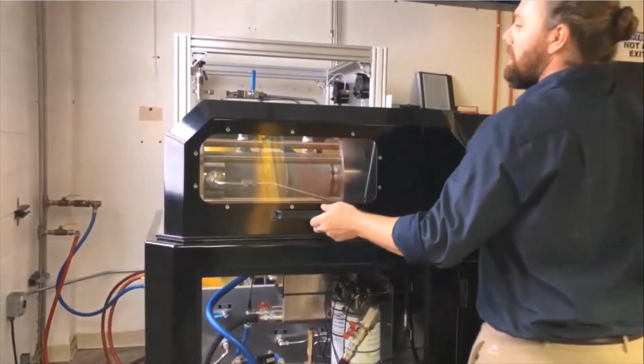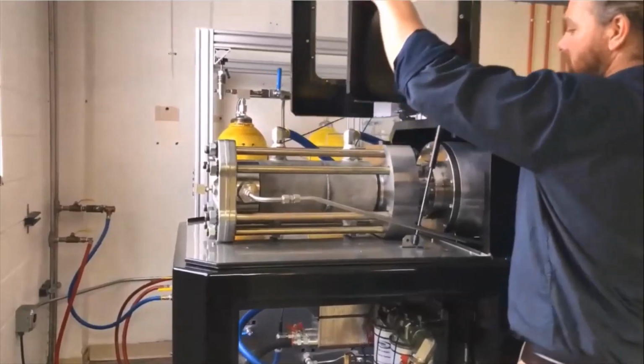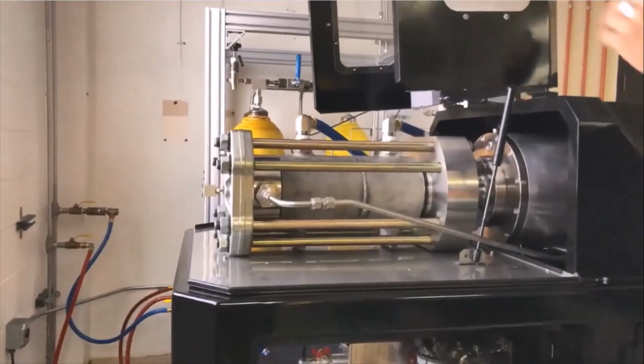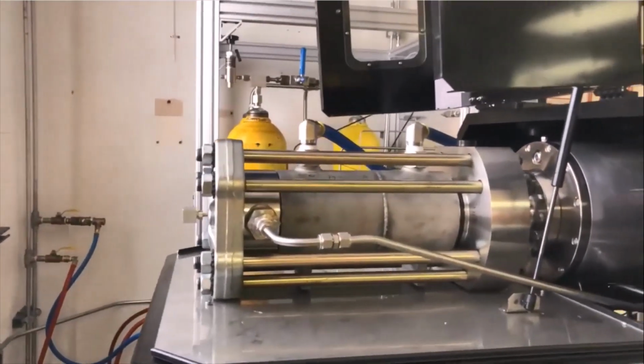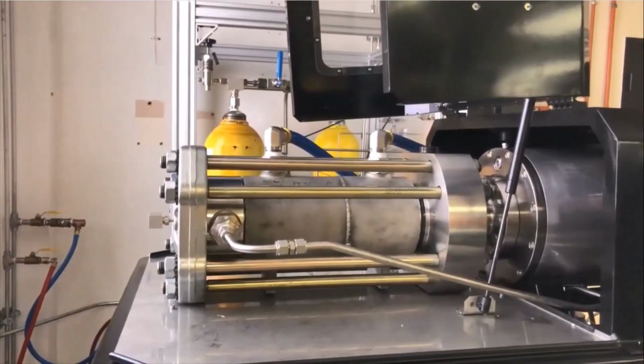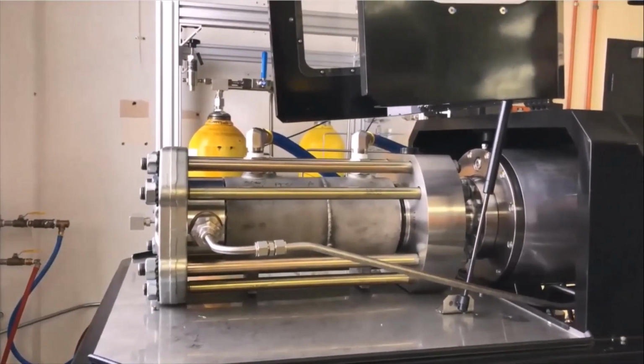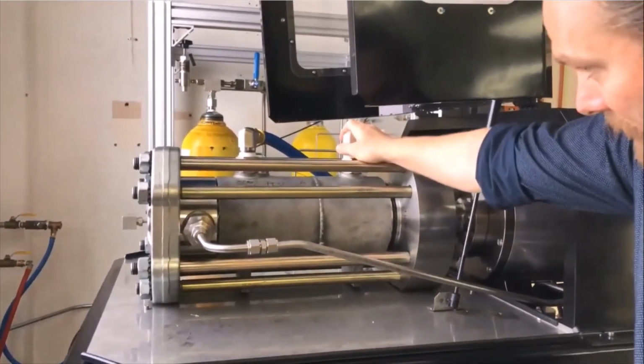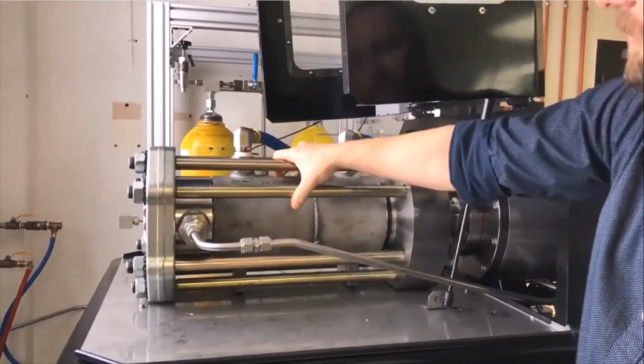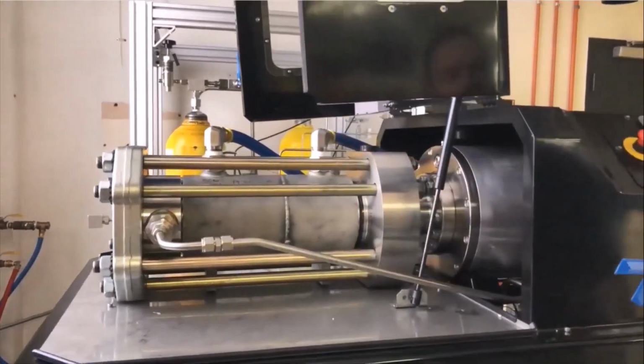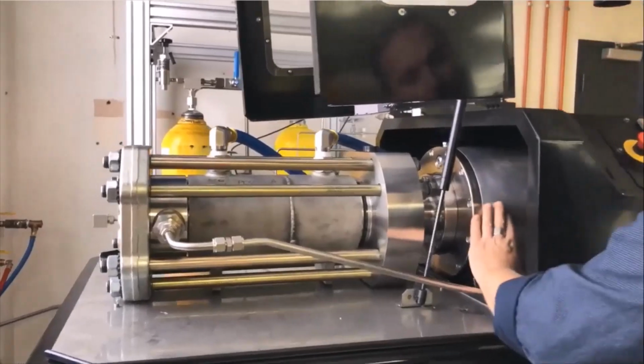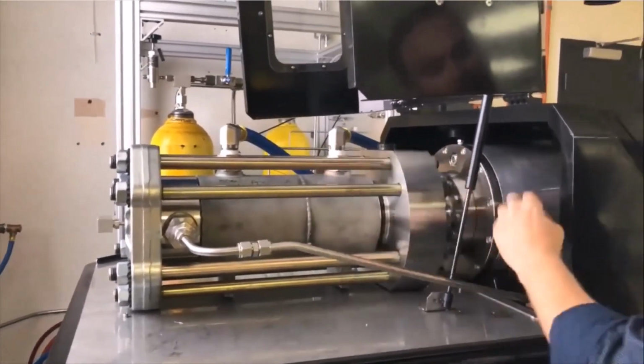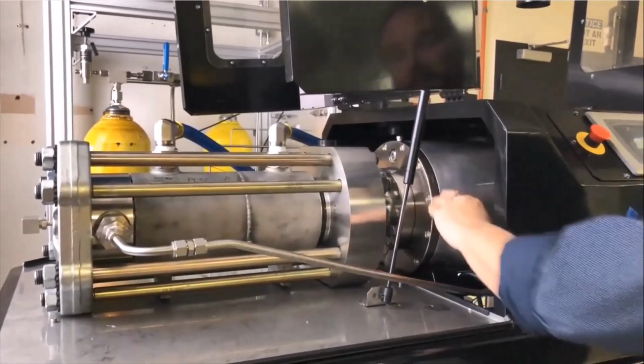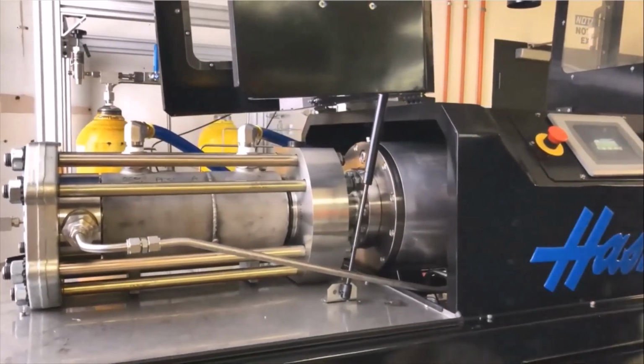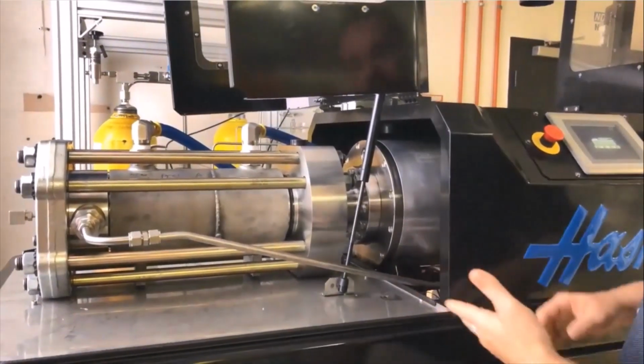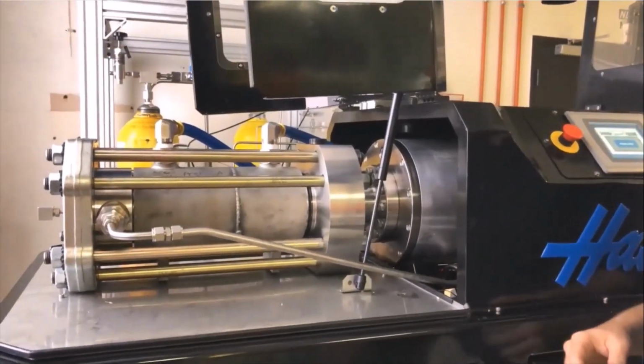Up top here, let's go through the gas sections. Right now we're looking at a single stage double acting gas booster. This is the QGD 90. Again, here's your cooling circuit going through the cooling jackets. Your servo drive. We have our distance piece gas section. The distance piece ensures there is no oil getting into your gas section. The oil is operating at lower than 30 psi.